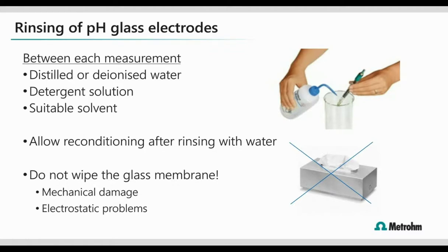It's also very important to avoid, as much as you can bear, wiping the glass membrane with a tissue. A lot of times I know we like to try to get that last drop off of the bulb, or we feel like we could really get it clean, it'll do better. But in reality, this practice can actually cause mechanical micro damages, which can change the property of the electrode. So micro scratches in the membrane can manifest as a noisy signal from your electrode. Also, you can load the electrode electrostatically, and once you've charged the electrode, it can be very difficult to regenerate it. So try as much as possible to avoid that.